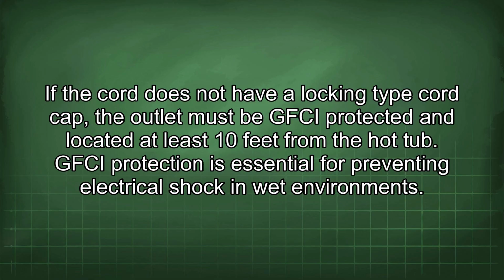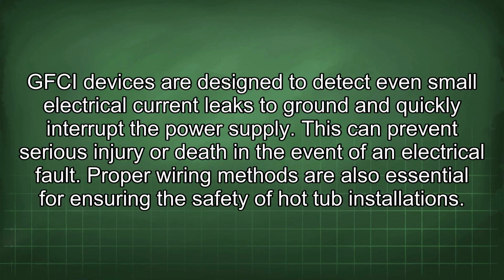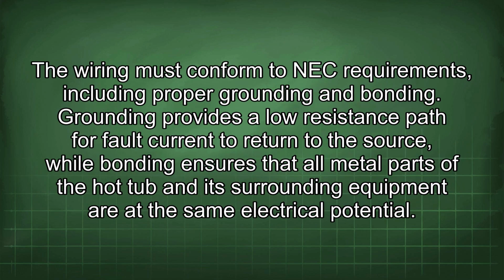GFCI protection is essential for preventing electrical shock in wet environments. GFCI devices are designed to detect even small electrical current leaks to ground and quickly interrupt the power supply. This can prevent serious injury or death in the event of an electrical fault. Proper wiring methods are also essential for ensuring the safety of hot tub installations. The wiring must conform to NEC requirements, including proper grounding and bonding.